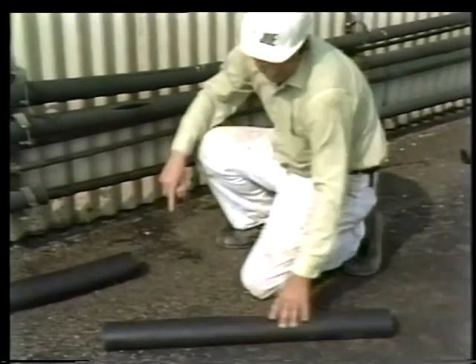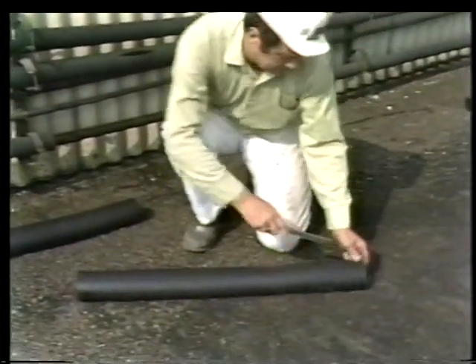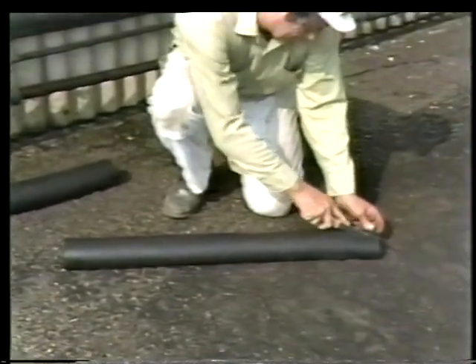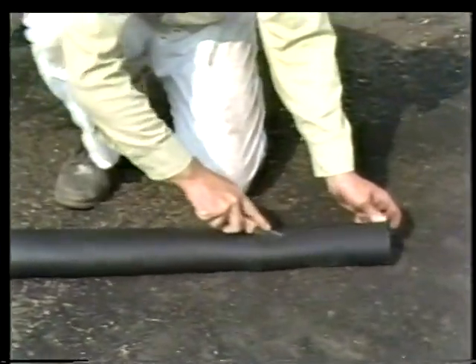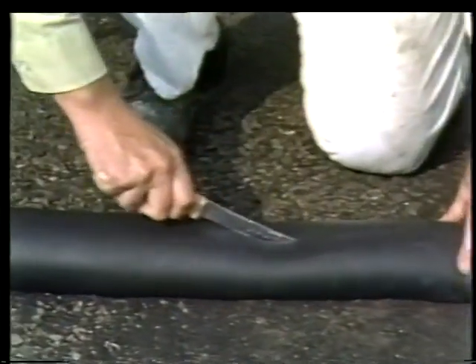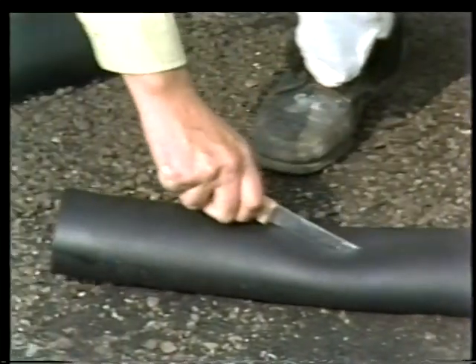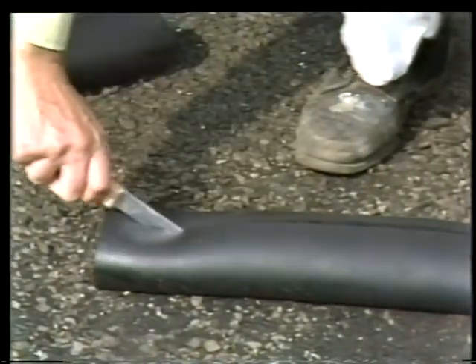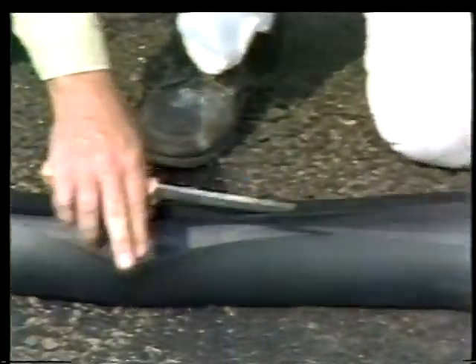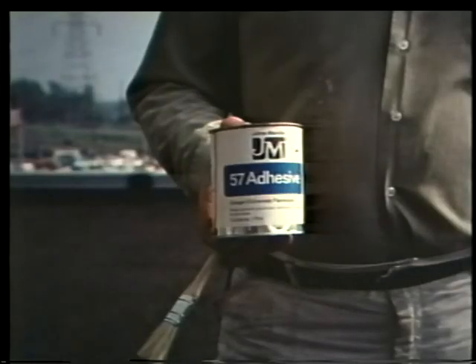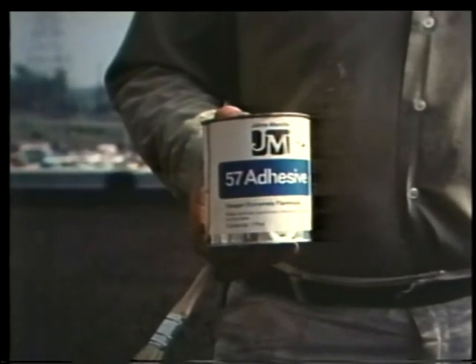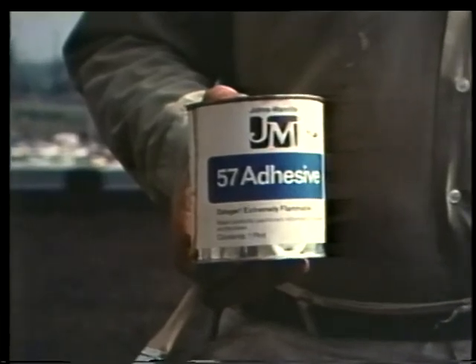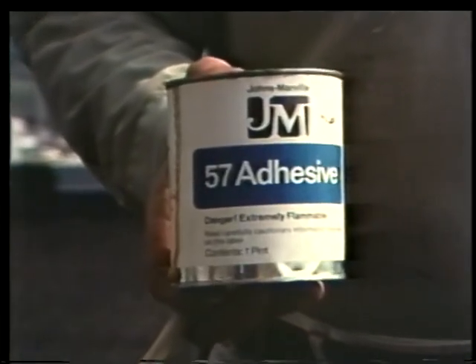This type of insulation comes in tubular sleeves. To fit it over a pipe that's already installed, it has to be slit along its length. On new installations, the rubber sleeves are usually just slipped over the ends of the pipes before the pipes are put up. To seal all the joints tightly, a special adhesive is used on all surfaces with rubber-to-rubber contact.